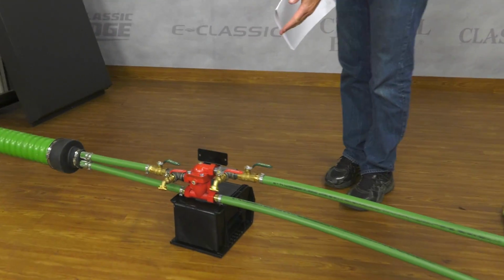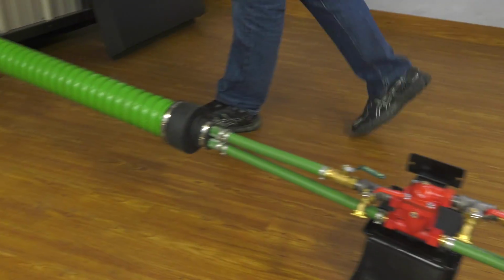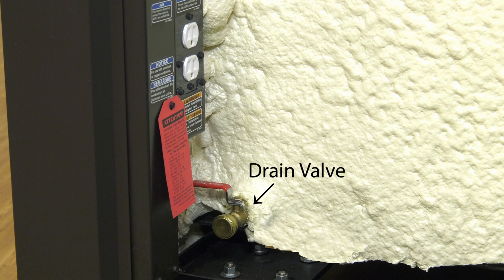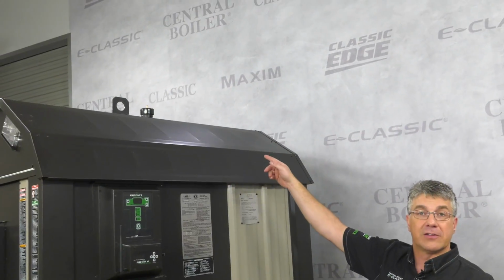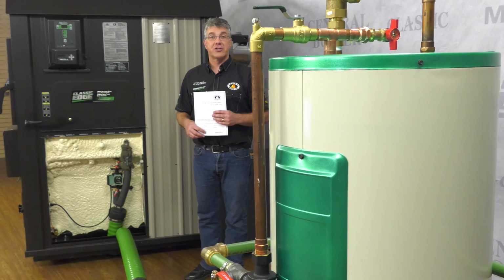There are 3 ways to add treated water to your outdoor furnace. You can add it indoors near the thermostatic valve. The second method is on the drain valve on the furnace itself. And the third method is through the vent pipe on top of the furnace. Whichever method you choose, it's important that the Corrosion Inhibitor Plus goes in first. For this demonstration, we'll use method 1, adding it through the return line as outlined in your installation guide. This will also make it easier to purge the system of air once you've completed the initial fill-up.